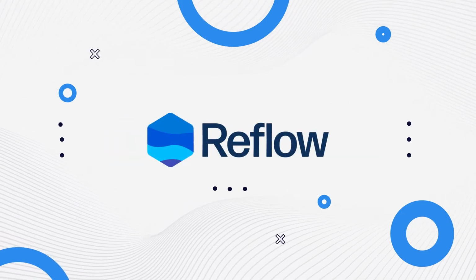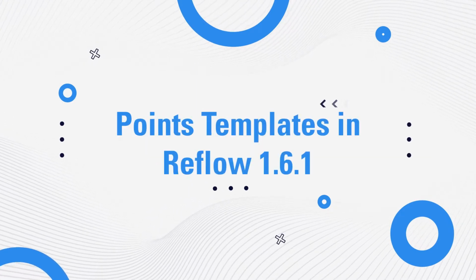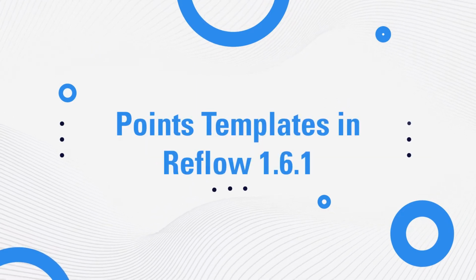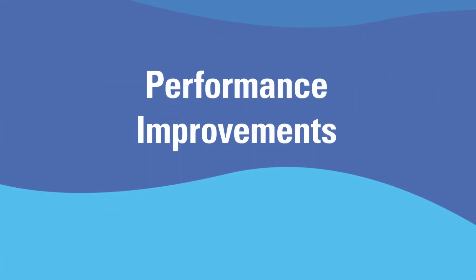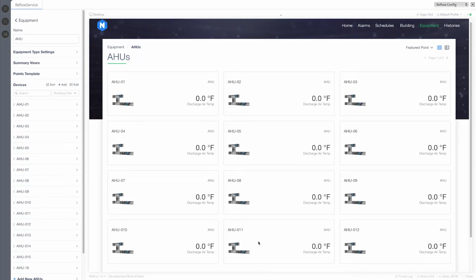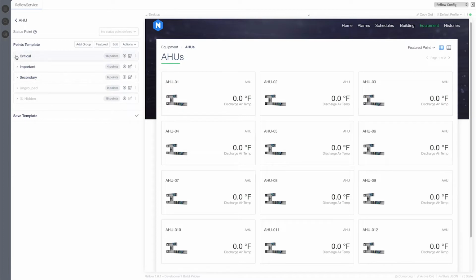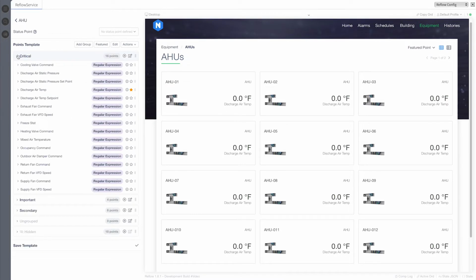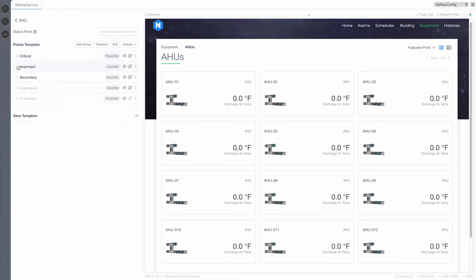In this video, we're going to take a look at some of the upcoming changes to point templates in Reflow 1.6.1. The first big change that you might not necessarily notice is that point groups, point order inside of groups, and point display names are saved at the template level when possible. These facets are no longer saved to the device's data object unless they deviate from the point template.